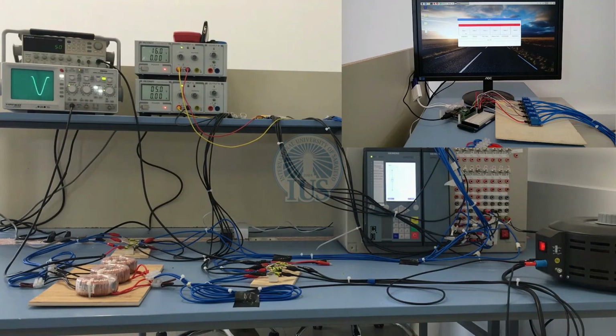So as you can see on the oscilloscope, for now we have a signal, a sine wave, 50 Hertz. There's the signal from an auto transformer. That means that there is voltage on the output side or low voltage side of the transformer. And when we press the first push button, the temperature trip, as you can see now the output on the oscilloscope is just a straight line, which means there is no more voltage there. So there is no voltage signal. The signal cannot pass because the circuit is opened. And when we again click the push button, turn it off, there is now voltage because the relays return to their initial normally closed position.